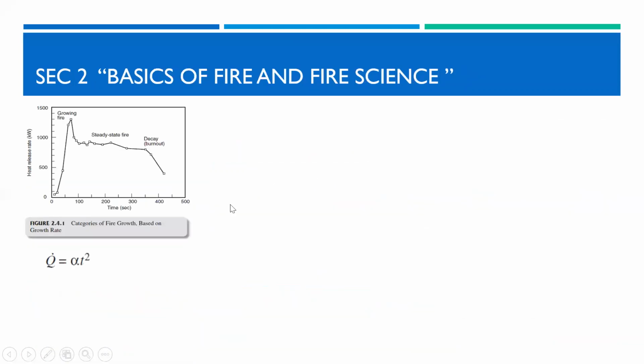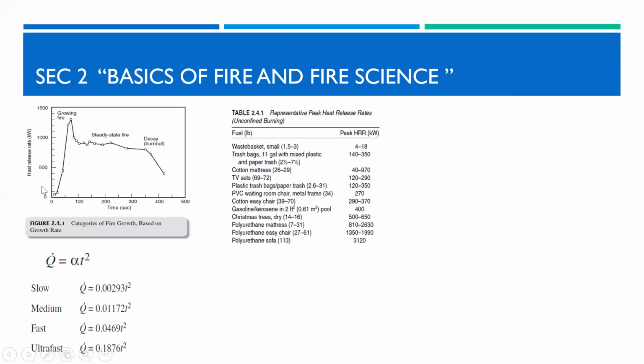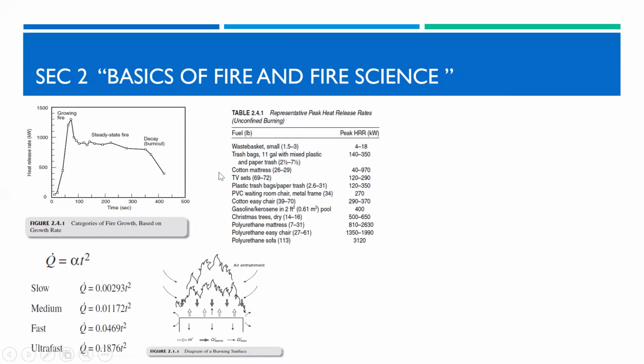Here, basics of fires, the curve of fire growth, heat release rate with time: rapid growth, then steady state, then decay, based on the famous equation Q equals alpha t squared, based on the type of fire: slow, medium, fast, ultra fast. And here we have the fuel type and the peak heat release rate in kilowatts. Here we have surface fire, how we can calculate the mass loss rate based on Q of flame minus Q loss of the surface, divided by the heat of gasification.